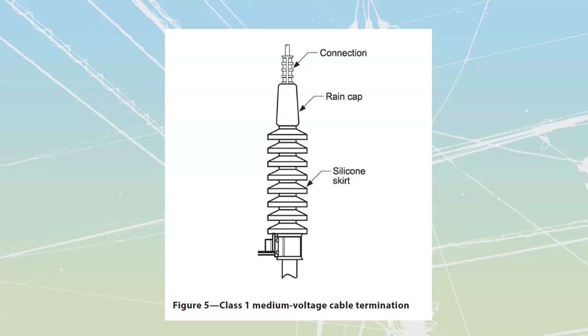Class 1 stress relief is going to distribute those electrical lines of flux, provide anti-tracking so we can't have as much surface creepage happening across it, and provide sealing against the environment. It usually uses some sort of impregnation or epoxy that prevents air pockets or moisture pockets inside, particularly in areas with rain or fog. So this would be stuff like outdoors - they usually have skirted silicone or porcelain.